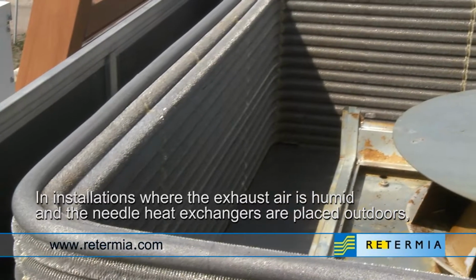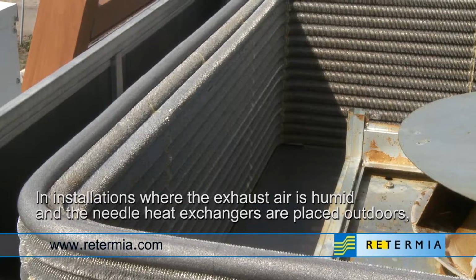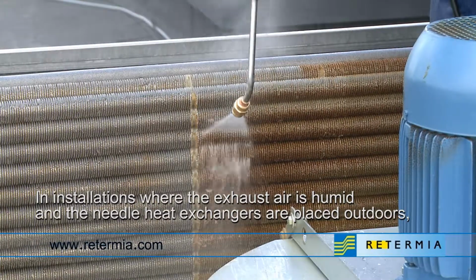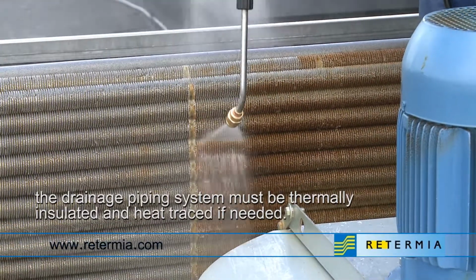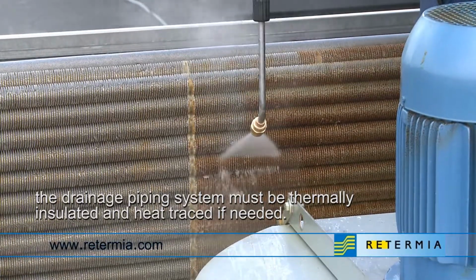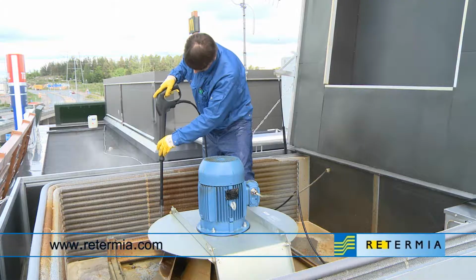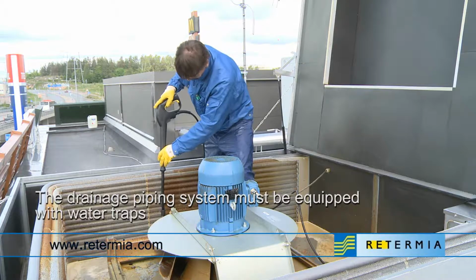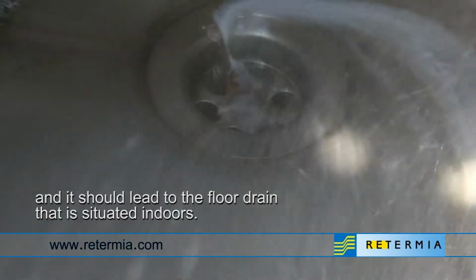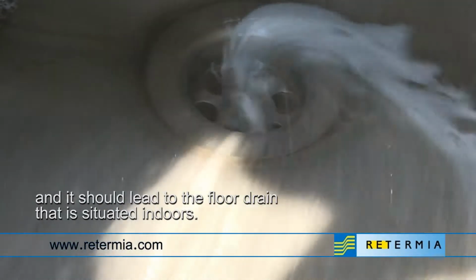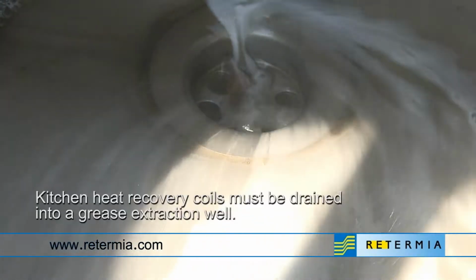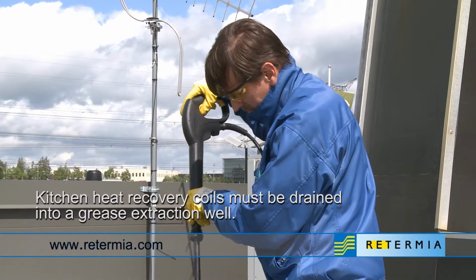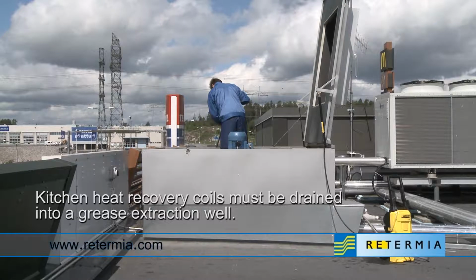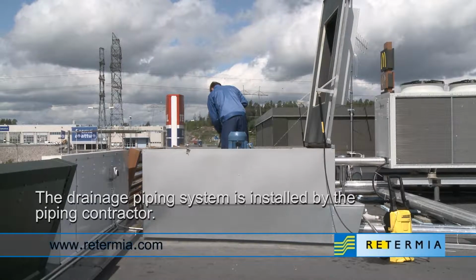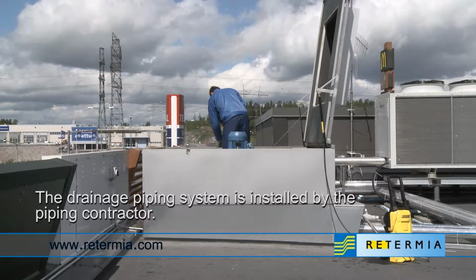In installations where the exhaust air is humid and the needle heat exchangers are placed outdoors, the drainage piping system must be thermally insulated and heat traced if needed. The drainage piping system must be equipped with water traps, and it should lead to the floor drain that is situated indoors. Kitchen heat recovery coils must be drained into a grease extraction well. The drainage piping system is installed by the piping contractor.